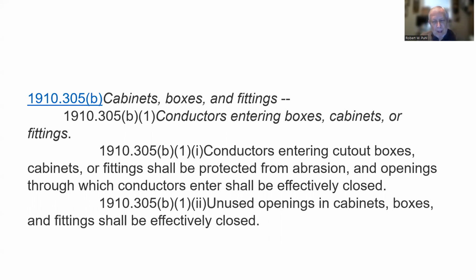Unused openings in cabinets, boxes, and fittings shall be effectively closed. Talked about that before. You've got a junction box, a panel like that, that has openings in it, and things have changed or been done erroneously or whatever. They knock out plugs and don't put them back in. That'll get you. The OSHA inspector will get you for that. And if there's more than one of them, he's going to look harder, because that's kind of what OSHA inspectors do. It makes sense. If they don't find anything, they're going to say, well, pretty good. If they're going to find stuff, I better look deeper. I'm finding this type of stuff. I don't know what I'll find if I look deeper. And that's just human nature.